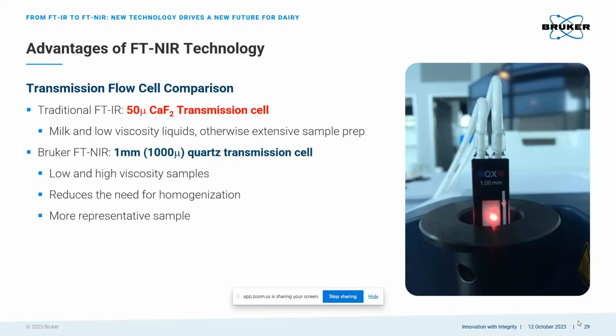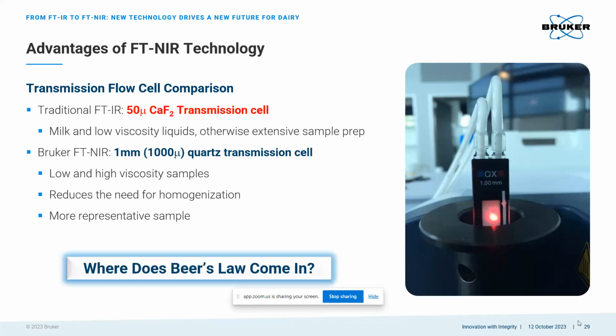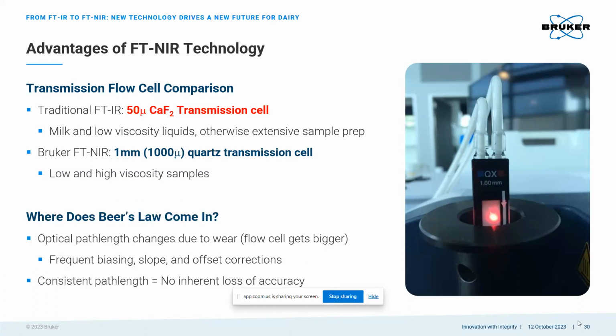However, for NIR flow cells, the cuvette material is quartz, which is resistant to any wear over time because it is not dissolved by water, solvents, or any component of milk or dairy liquid products. And additionally, the particles have no abrasive effect on the inside surfaces of the cell. So, what does this have to do with the integrity of the measurement? Well, again, let's think back to Beer's law. From Beer's law, we can see how changing the path length can impact our results. And this is especially true when the path length is already so small to begin with.